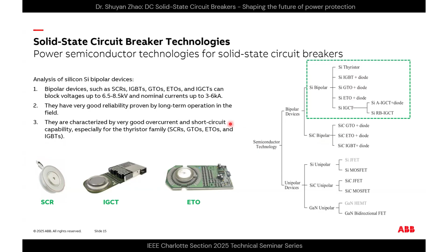Next is the medium voltage solid state circuit breaker based on IGBT devices. IGBT is also a robust device with really high power rating achievable. For example, in this work, an IGBT with a blocking voltage of 4.5 kV is used in a medium voltage bus-tie solid state circuit breaker, and the architecture is shown here for electric ships. The solid state breaker demonstrated experimental results with a system voltage up to 10 kV DC and 1000 amps, with only a 0.8 microsecond opening time. That's very fast. However, IGBTs still exhibit relatively higher conduction losses than thyristor-based solutions.